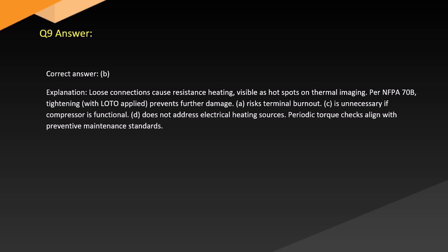Answer. Correct answer: B. Explanation. Loose connections cause resistance heating, visible as hot spots on thermal imaging per NFPA 70B. Tightening with LOTO applied prevents further damage. A. Risks terminal burnout. C. Is unnecessary if the compressor is functional. D. Does not address electrical heating sources. Periodic torque checks align with preventive maintenance standards.